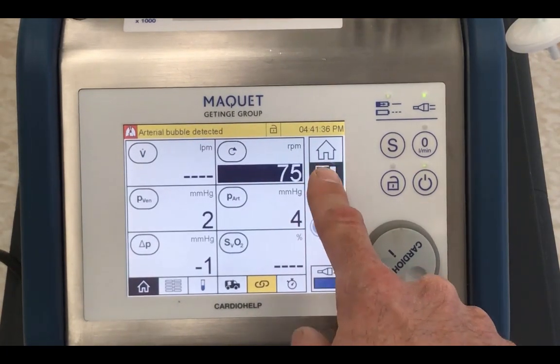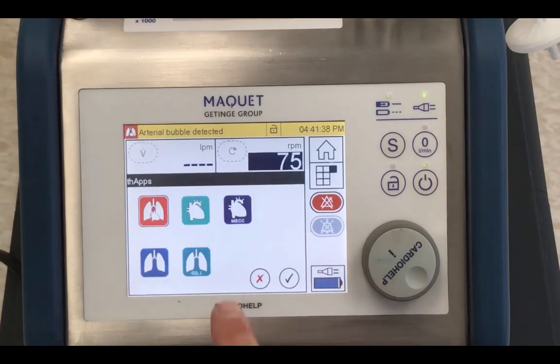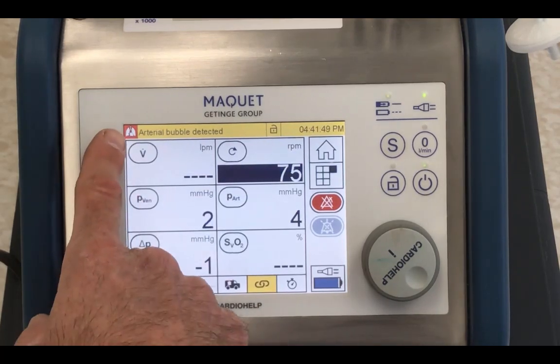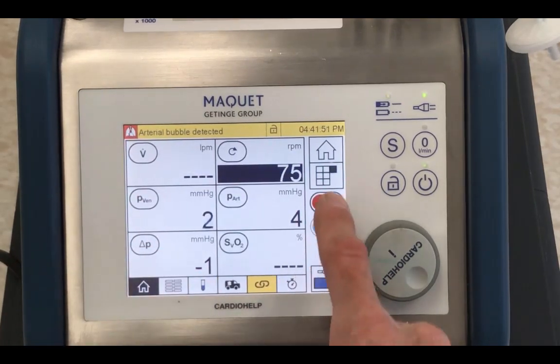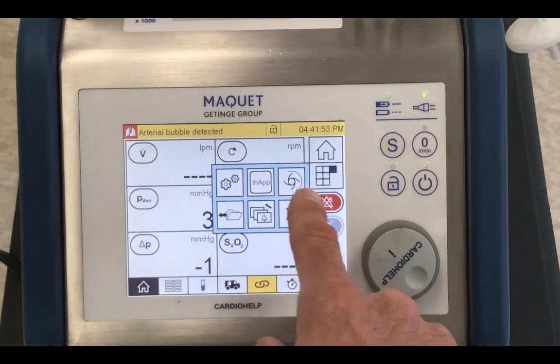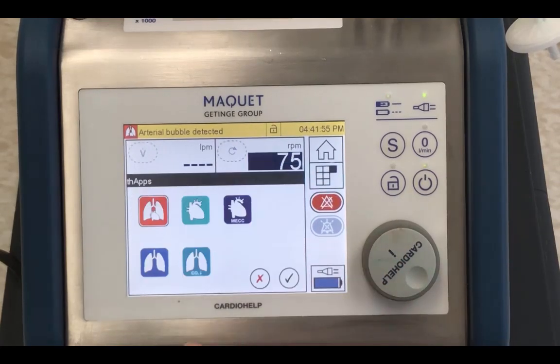Let me show you what happens with that X. This is a process that's preserved throughout the system. If I select the blue, let's say I want to go to veno-venous, and I hit the X to get out of this screen, it's still in red. It's still in the VA ECMO mode. If I wanted to switch to blue, I need to go to the Tetris, I need to go to the therapy application button, I need to select the veno-venous, and I get out of this screen by entering the data.